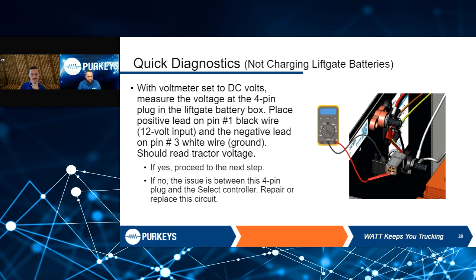And then measuring at the 4-pin plug. If you have the older style DC-DC converter, you can actually unplug the plug and measure at that 4-pin plug. So with your voltmeter, measure voltage on pin number 1, which is your input, and the negative lead on pin number 3, which is your ground. Now that should read tractor voltage. If yes, proceed to the next step. If no, the issue is between the 4-pin plug and the select controller, so you'll need to replace that circuit.